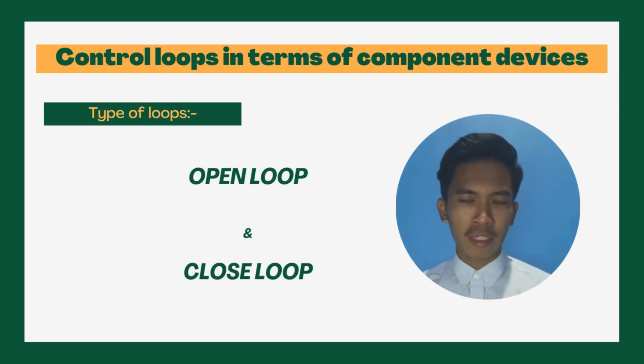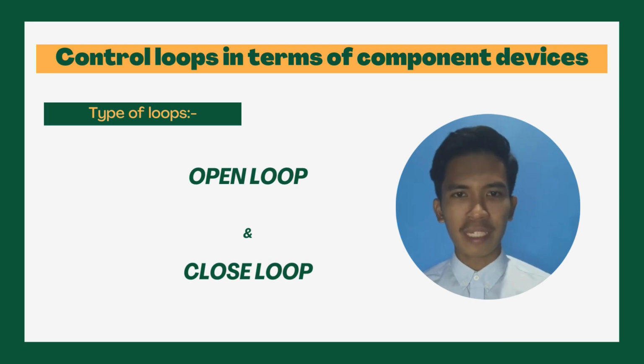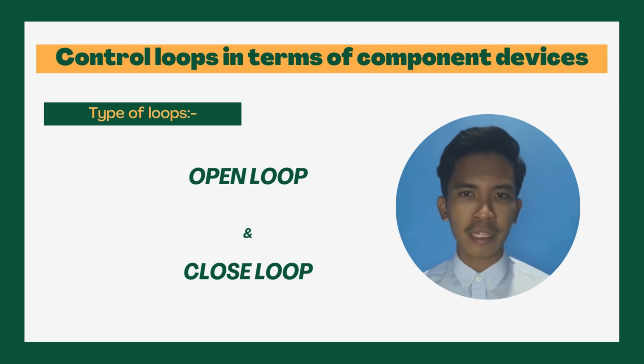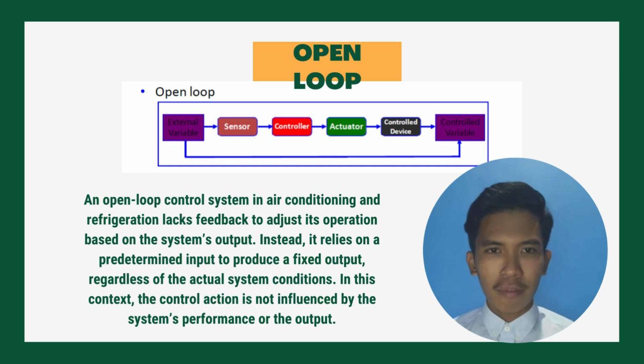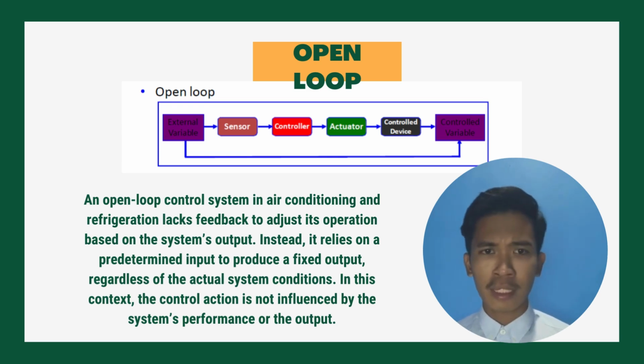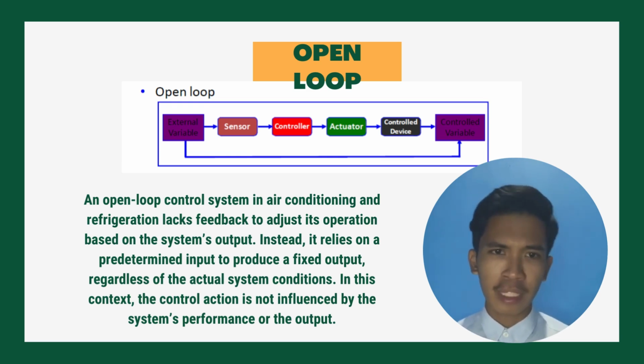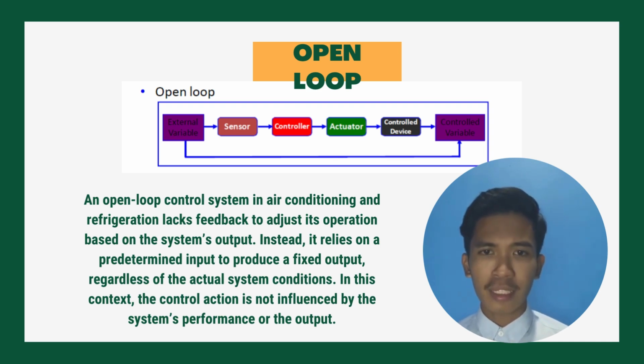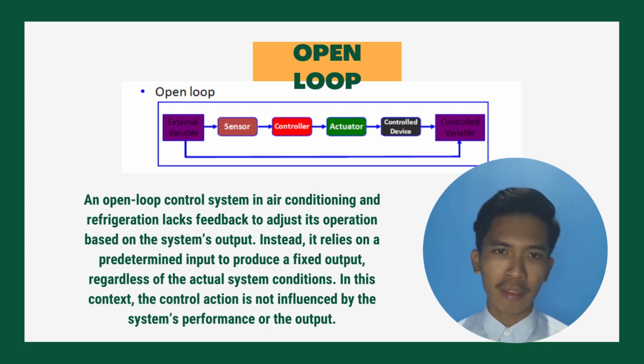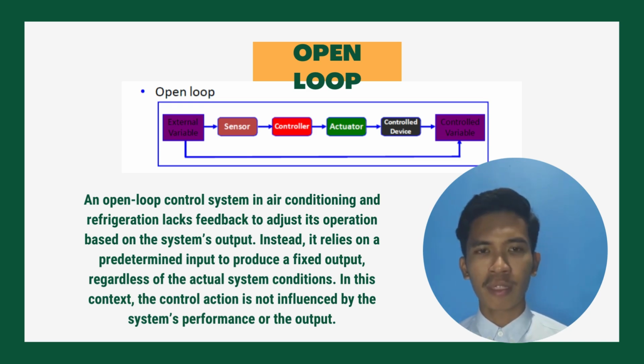Right now, we go to the control loops in terms of component device. There are two types of control loops. The first one is open loop and the second one is closed loop. Now, I will explain about the open loop control. An open loop control system in air conditioning and refrigeration lacks feedback to adjust its operation based on the system output. Instead, it relies on a predetermined input to produce a fixed output, regardless of the actual system condition. In this context, the control action is not influenced by the system performance or the output.